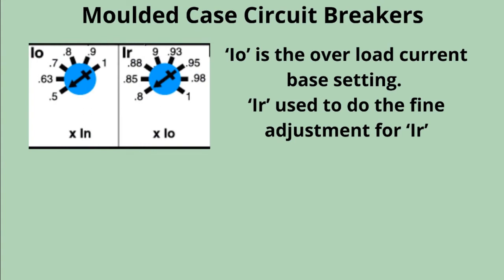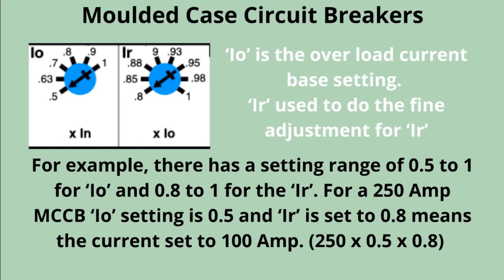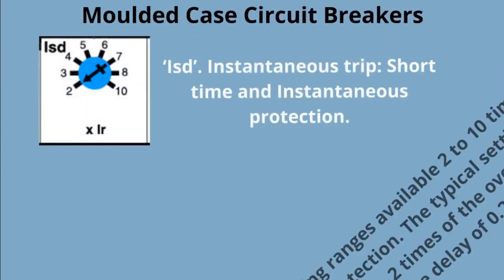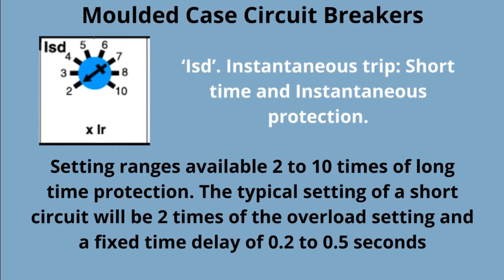I-O is the overload current base setting. For example, there is a setting range of 0.5 to 1 for I-O. For a 250 amp MCCB, if I-O is set to 0.5 and I-R is set to 0.8, the current set to trip is 100 amp. ISD covers instantaneous trip, short time, and instantaneous protection. The setting range is available from 2 to 10 times of long time protection. The typical setting for short circuit will be 2 times of the overload setting, with a fixed time delay of 0.2 to 0.5 seconds.